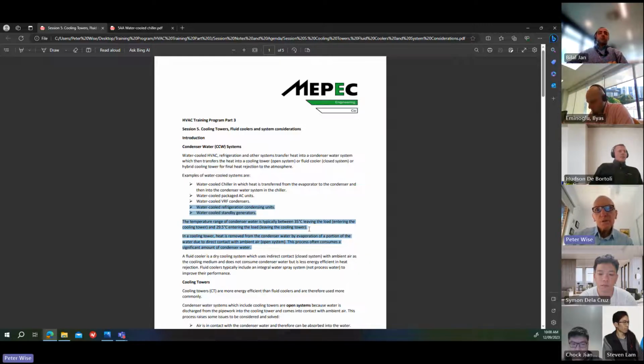That's pretty typical. It comes from the old Fahrenheit scale of 95 to 85, if you're interested, but that's where it came from. So they've kept those temperatures into the SI unit system. In a cooling tower, heat is removed from the condenser water by evaporation of a portion of the condenser water, due to direct contact with ambient air. So this is why it's an open system. The air and water come in contact with each other. This process often consumes a significant amount of condenser water.